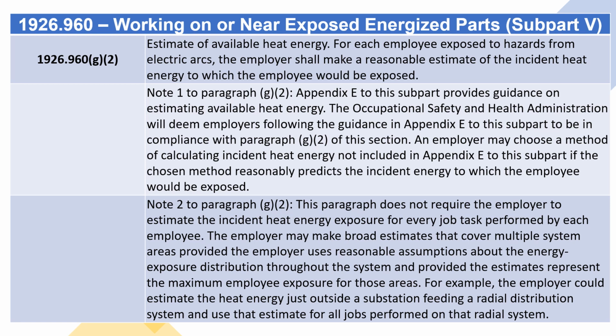Note 2 to paragraph (g)(2): This paragraph does not require the employer to estimate the incident heat energy exposure for every job task performed by each employee. The employer may make broad estimates that cover multiple system areas provided the employer uses reasonable assumptions about the energy exposure distribution throughout the system and provided the estimates represent the maximum employee exposure for those areas. For example, the employer could estimate the heat energy just outside a substation feeding a radial distribution system and use that estimate for all jobs performed on that radial system.